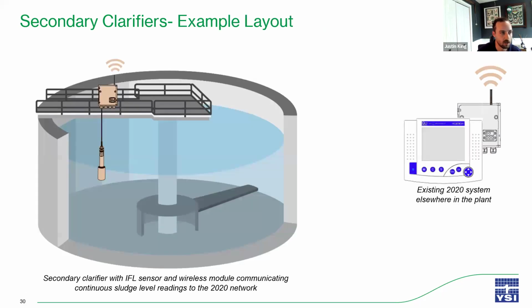And then, like I said, a lot of secondary clarifiers in typical wastewater treatment plant layouts are a lot farther away from the rest of the process. So it can often be hard or taxing just to run cabling and wiring out to these remote locations in the plant. What we have with IQ SensorNet is remote or wireless modules that use a radio frequency to communicate over distances of up to 100 meters. As long as these two modules on the screen here have line of sight, it will communicate the sludge level height back to our controller, which might be sitting somewhere else in the plant, maybe on the activation basins or the aeration basins, or right outside of a control house.